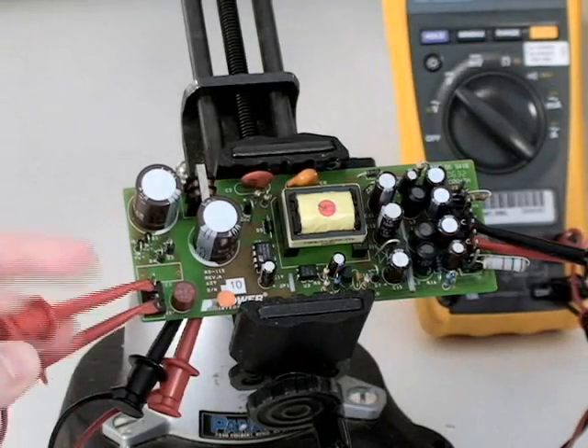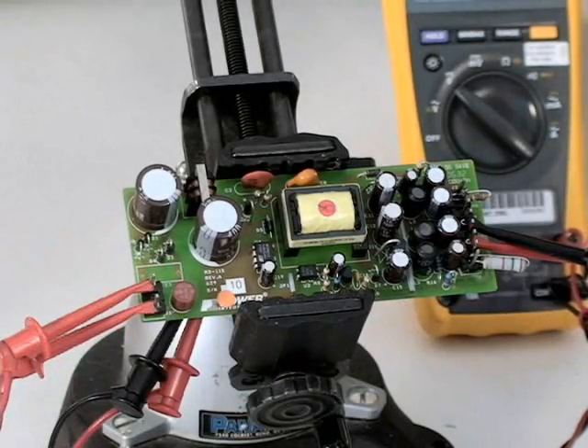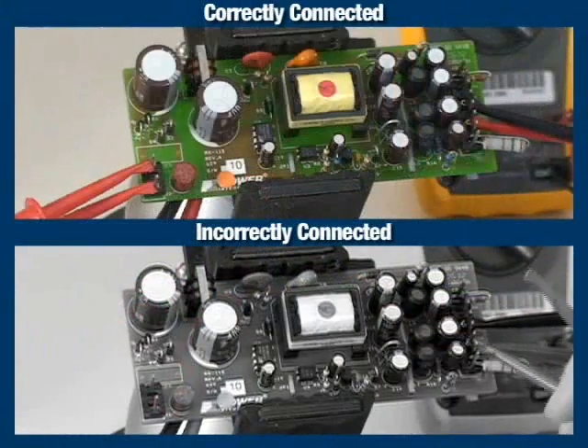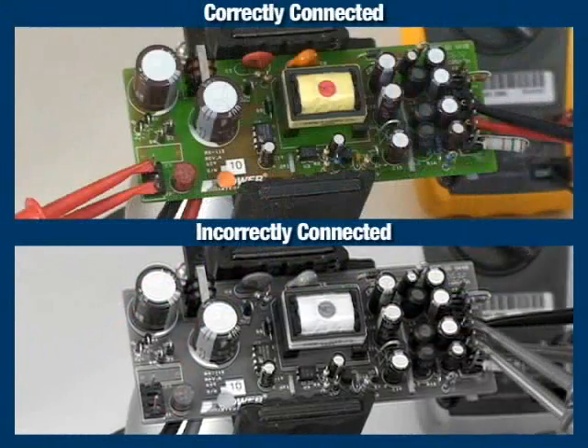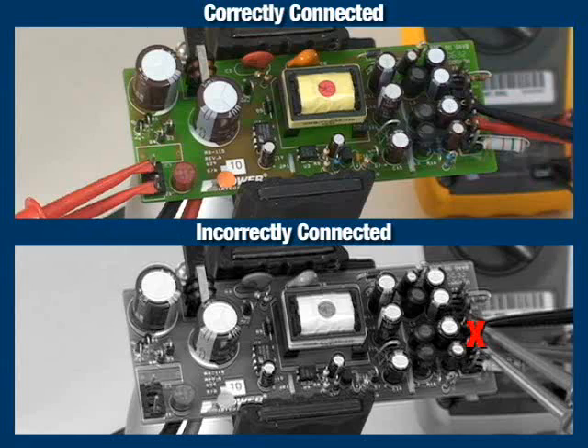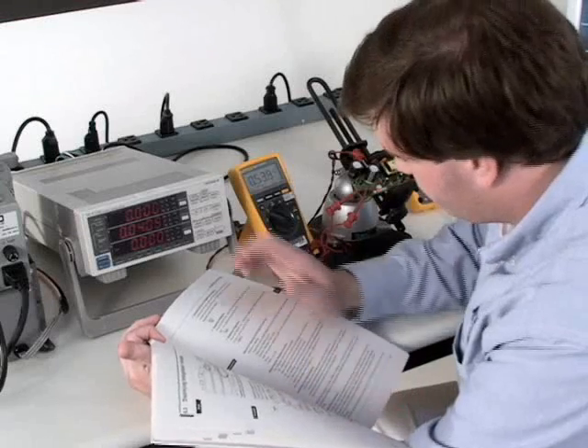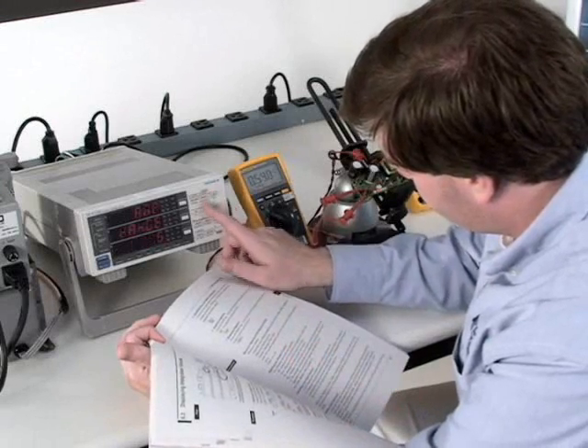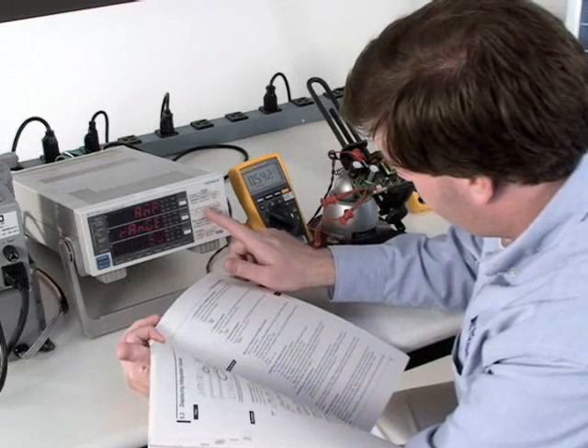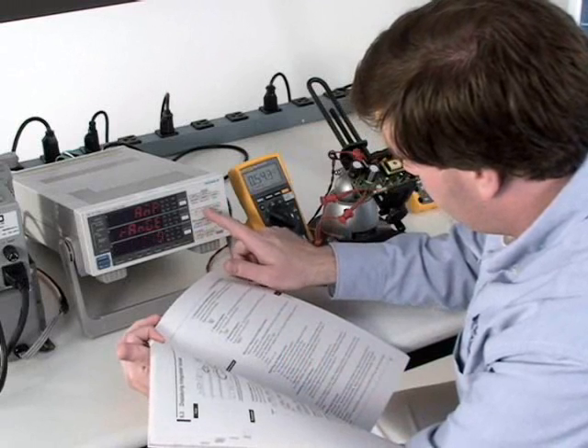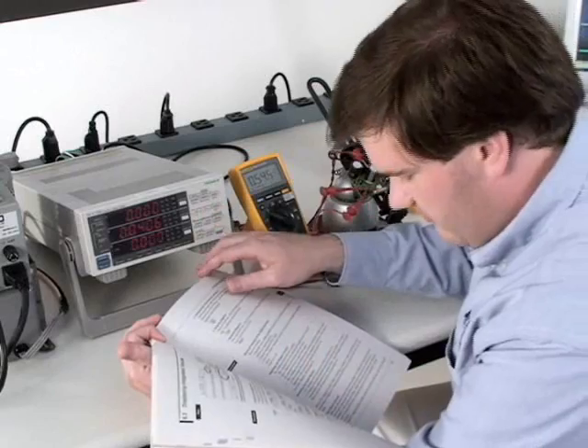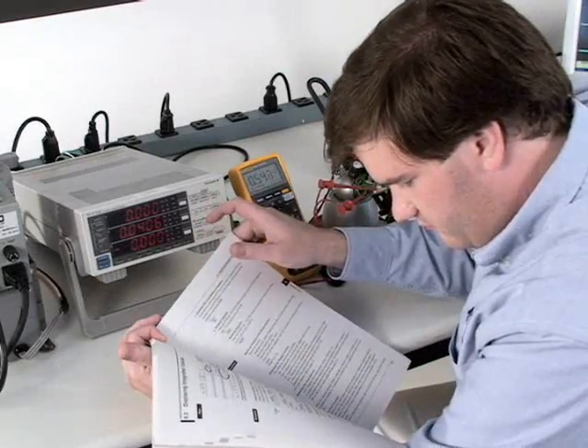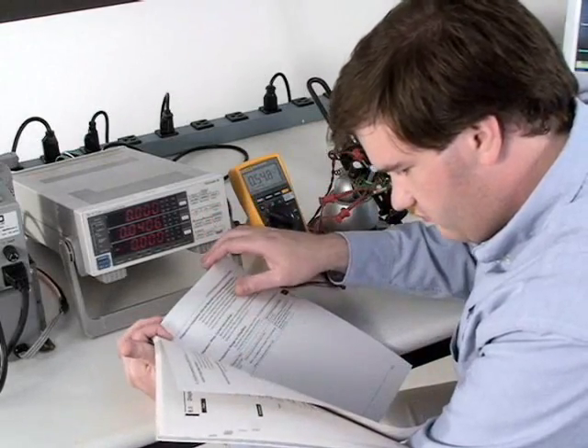Be sure the AC input is correctly connected to the power supply input terminals and not the DC output. Improperly connecting the AC input can severely damage your supply. We'll also need to measure AC input power for this test. If you have a wattmeter, refer to its operator's manual for instructions on how to install it in your AC input path and configure it to measure AC voltage, current, and input power.